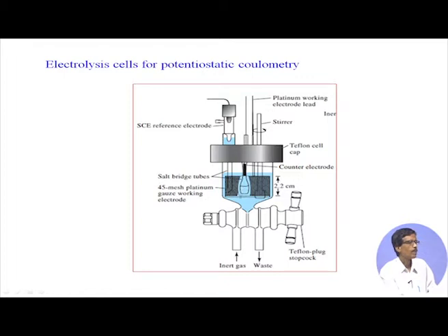But for coulometric measurements, the surface area of the electrode has to be very high. So, you have the corresponding platinum wire gauze, which also means less adsorption. It is a fine mesh wire gauze system, and then you have the magnetic stirrer from the top, the motor is over here. So, the motor is connected to this stirrer and the stirrer is giving you the stirring condition.